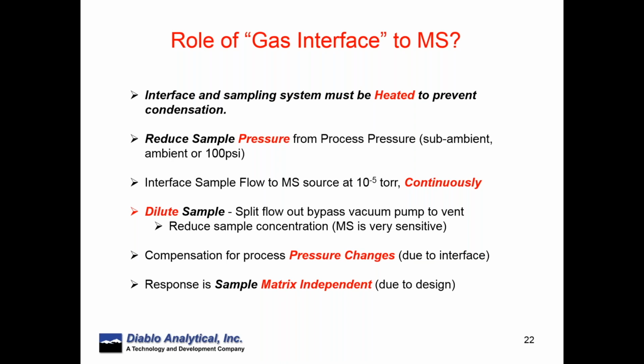device that runs at 10 to the minus 4, 10 to the minus 5 torr. So somehow we have to very reproducibly and consistently reduce the pressure. We also have to reduce the sample flow. Mass spec is very sensitive, so we're going to end up with a very small amount of sample actually ever reaching the mass spectrometer. But we need to do this continuously, and we're going to have to dilute the sample.